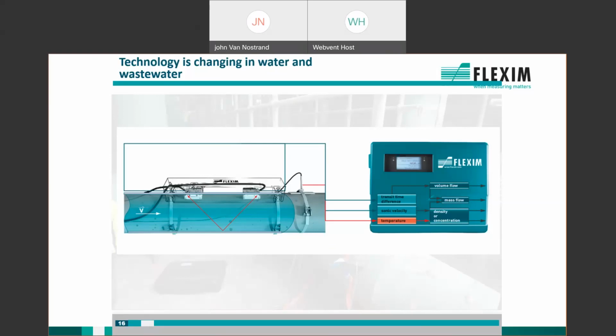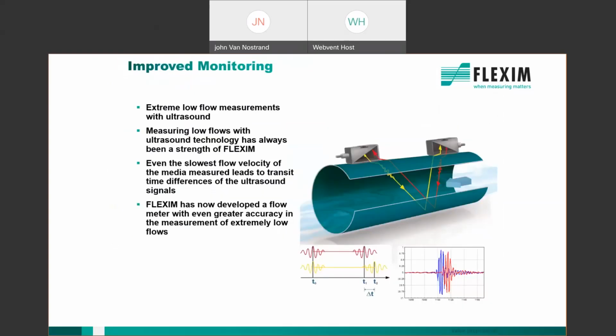Under flowing conditions from outside the pipe, we correlate the sound speed of the media to the temperature of the media. When the temperature changes, we report that, and that's about plus or minus 0.35 degrees F. So we not only get an accurate flow measurement, but we can also correlate the temperature and report that too. That's becoming increasingly important, especially with biological growth and also predicting how much hypochlorite might be necessary to treat the water.